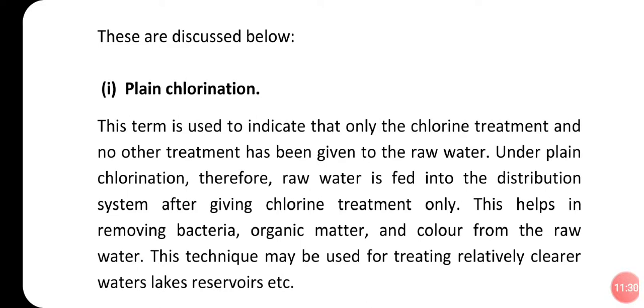So where there is little quantity of water and little contamination of water, in such case plain chlorination will be done. No other treatment is given. What are the other treatments? Aeration, filtration, sedimentation, and all these treatments are there. So plain chlorination means all other treatments are not essential because water may not be containing much bacteria. So in such cases plain chlorination will be used. Under plain chlorination, raw water is fed into the distribution system after giving chlorine treatment only. Here only chlorine treatment is given, no other treatment is given.